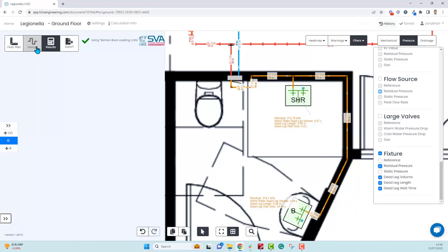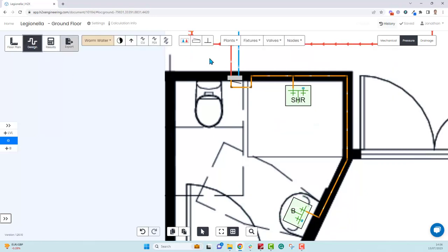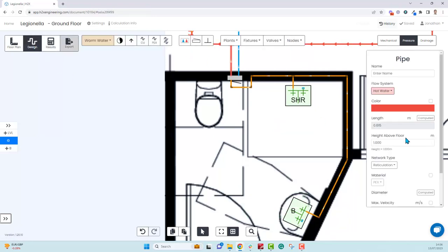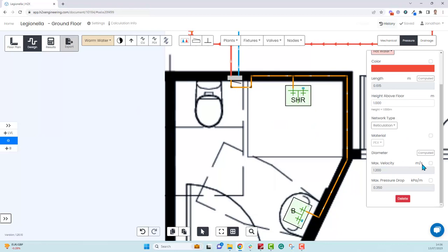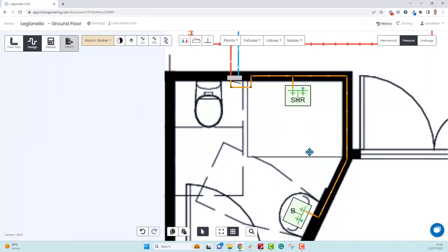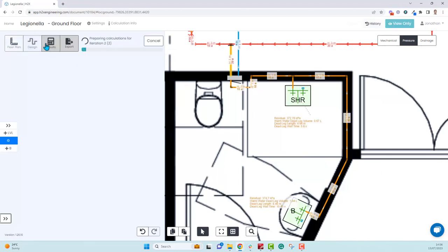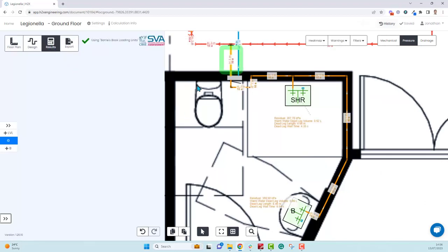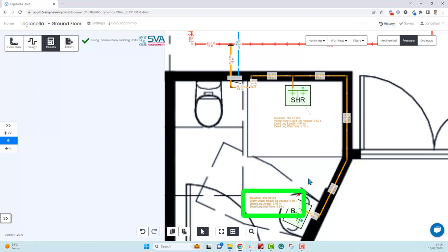So let's look now if we go in and increase the velocity of this one pipe from 1.2 to 1.5 meters per second. This gives us a 16 millimeter pipe and reduces the dead leg down below one liter to 0.89 liters.